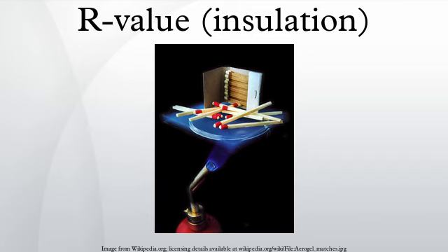On the other hand, the conductive and convective heat loss modes play a more significant role during the cooler months. At such lower ambient temperatures, the traditional fibrous, plastic and cellulose insulations play by far the major role. The radiative heat transfer component is of far less importance, and the main contribution of the radiation barrier is in its superior air tightness contribution. In summary, claims for radiant barrier insulation are justifiable at high temperatures, typically when minimizing summer heat transfer. But these claims are not justifiable in traditional winter conditions.